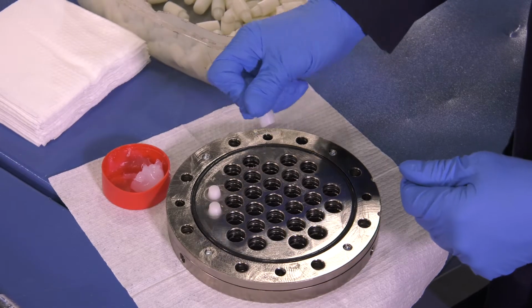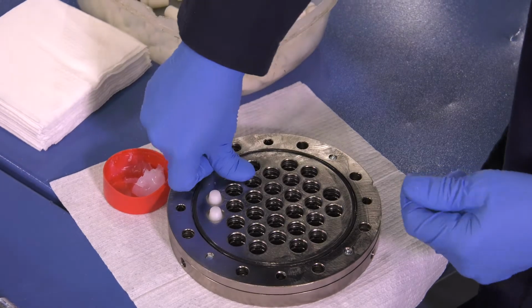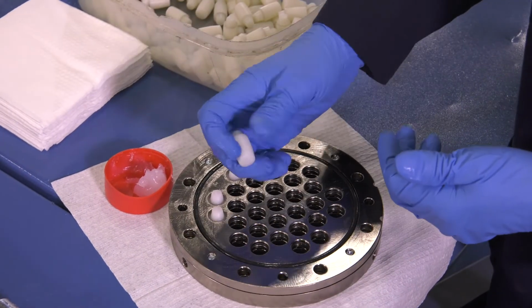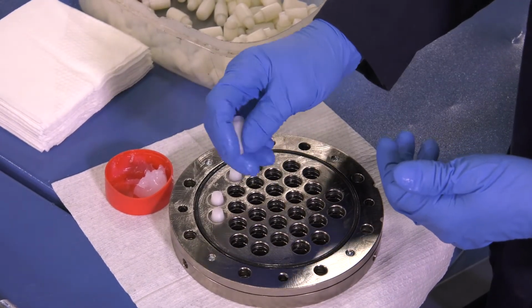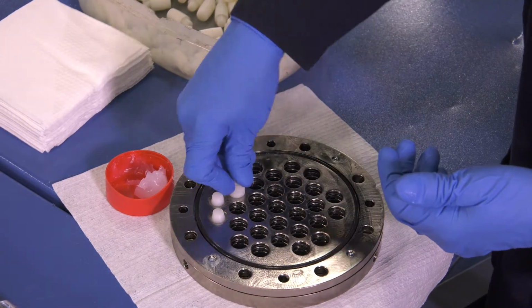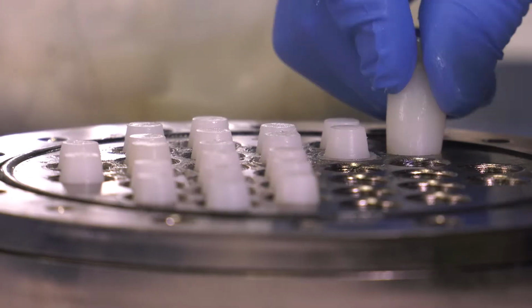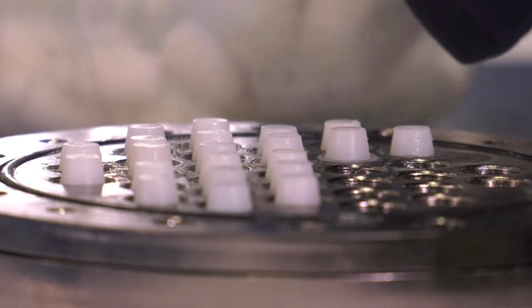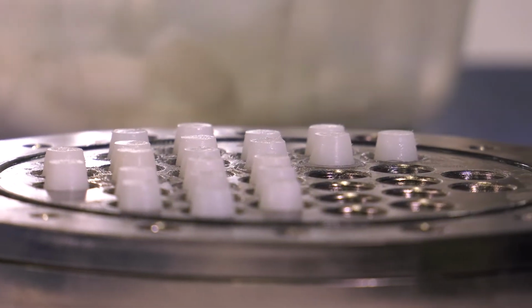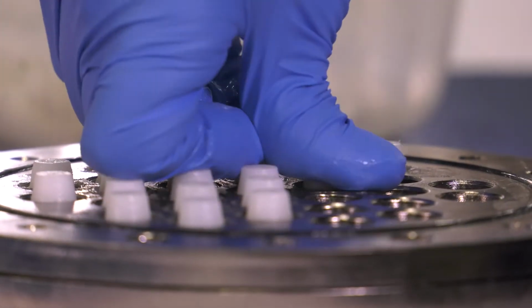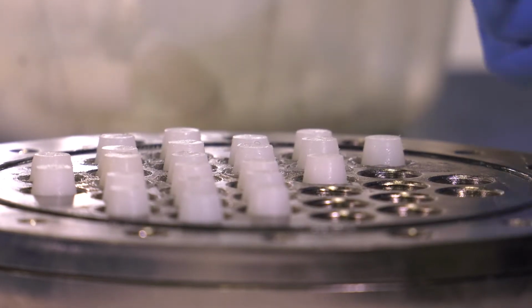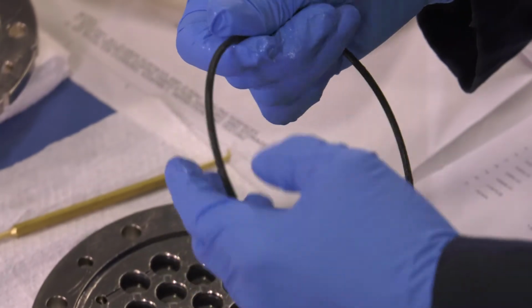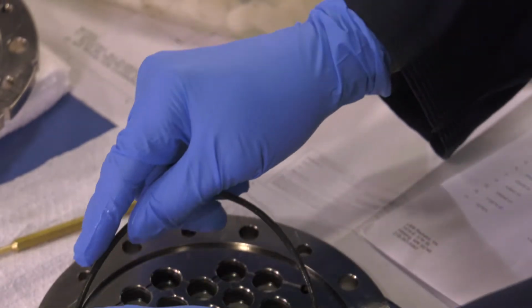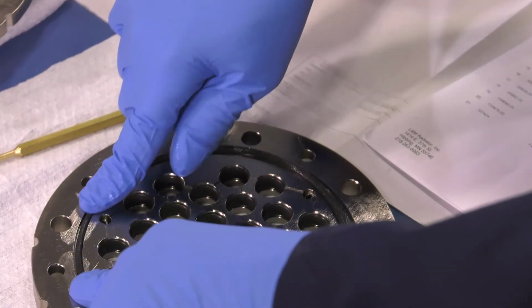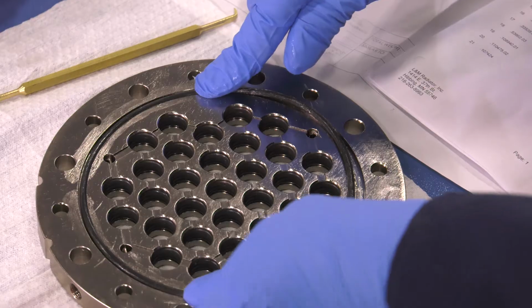Lay both header plates down on a clean surface with the narrower O-ring groove facing up. Apply a thin layer of lubricant to the plastic assembly bullets and install them into all the tube holes in both header plates. Tapered ends of bullets go into the holes first. Install new header-to-end flange seals into the header plate. Add a slight amount of assembly lube to hold the seal in place.